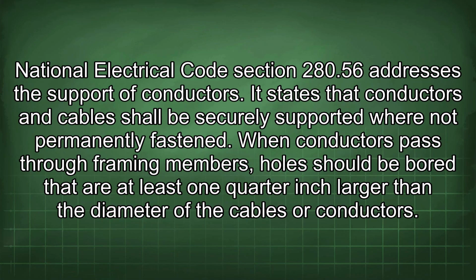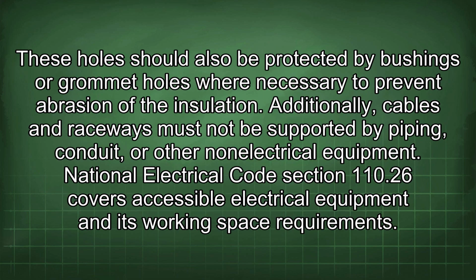National Electrical Code Section 280.56 addresses the support of conductors. It states that conductors and cables shall be securely supported where not permanently fastened. When conductors pass through framing members, holes should be bored that are at least 1/4 inch larger than the diameter of the cables or conductors. These holes should also be protected by bushings or grommet holes where necessary to prevent abrasion of the insulation. Additionally, cables and raceways must not be supported by piping, conduit, or other non-electrical equipment.